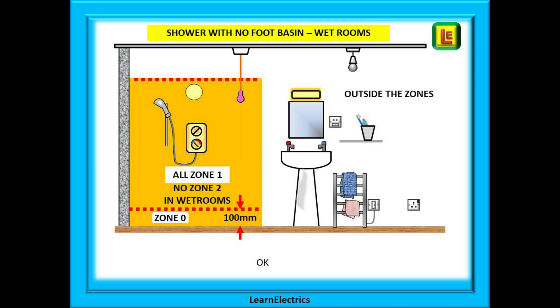For a shower with no footbasin, as in wet rooms, things are slightly different. The height of Zone 0 is taken as 100 millimetres, and all the space above up to 2.25 metres is Zone 1. There is no Zone 2 in a wet room — we go straight to the outside zones.